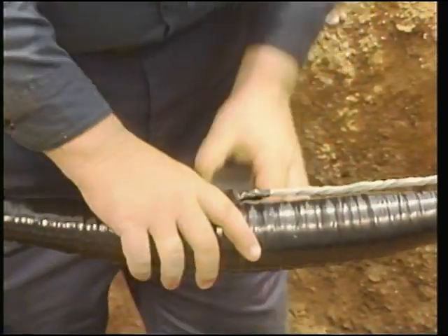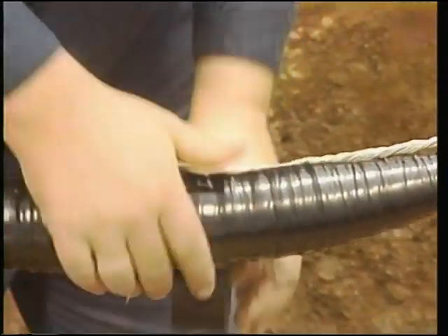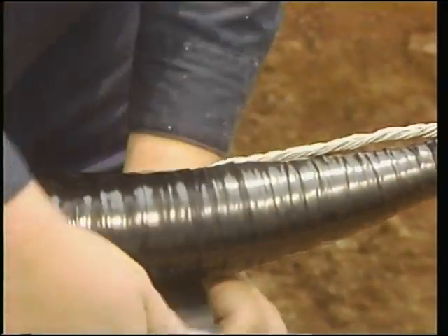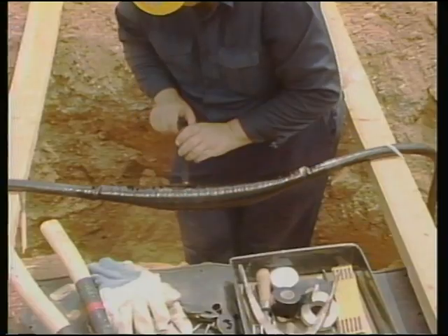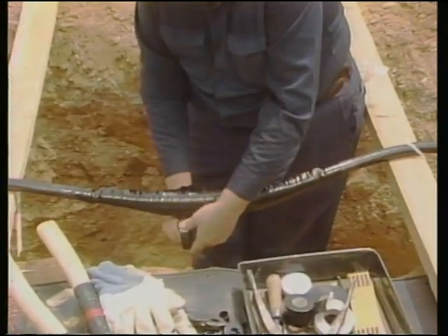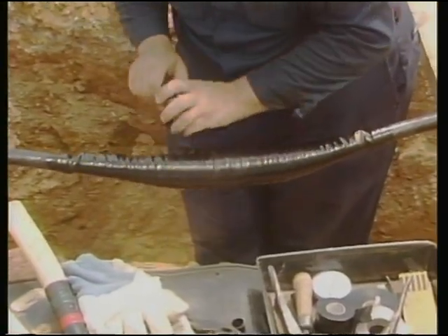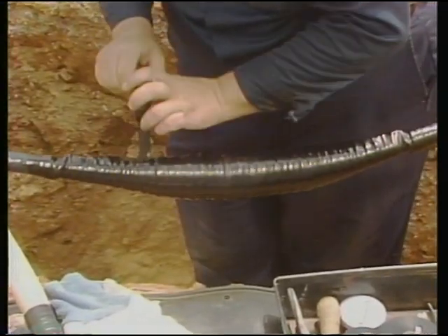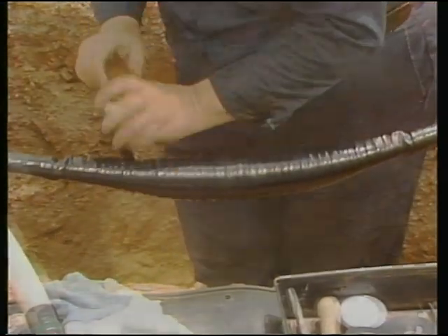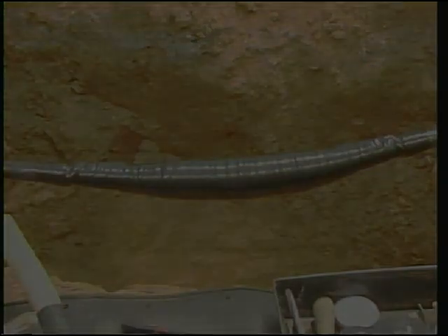The next layer to be applied is made of rubber insulating tape. This layer is applied over the concentric wires, overlapping the cable jacket according to the splicing instructions. A layer of plastic vinyl tape is also applied over the high voltage rubber splicing tape so that it is overlapping onto the cable jackets. The rubber and plastic tapes replace the original cable jacket and help protect the splice from environmental hazards. The tape splice is now complete, and the cable's original design characteristics have been restored.